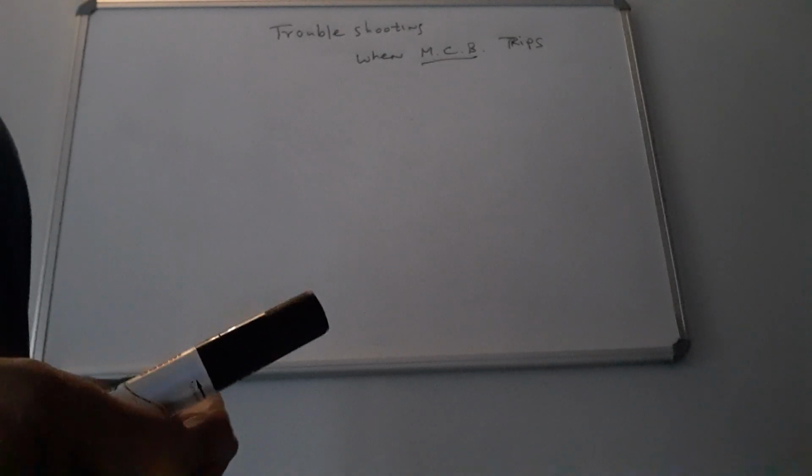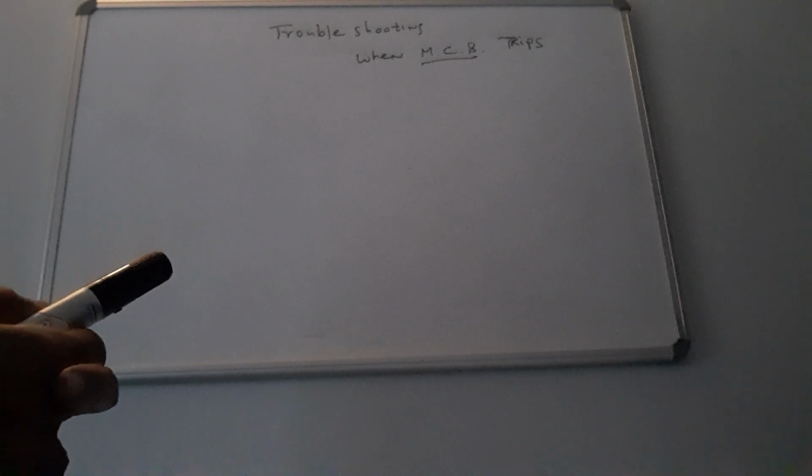If the M.C.B trips, that means there is a short circuit in the light, for which electrician will be required. And if it does not trip, that means that there is no short circuit in the light. And then you can power on the third item, which is the plug point. And now if the M.C.B trips, that means there is short circuit in the plug point.